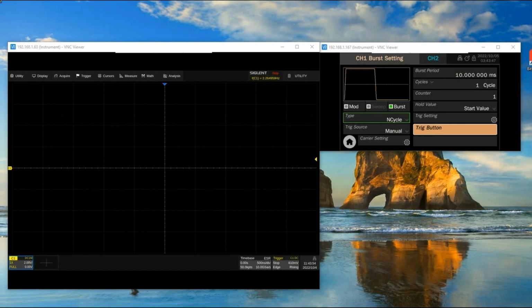There is a video already on sequence mode directly, so I'm not going to go into gory detail about that. But I would like to let you know that there's a really easy way to set a number of frames, and once that number of trigger events has been captured, the instrument will automatically go into stop. So I'd like to quickly go through that.